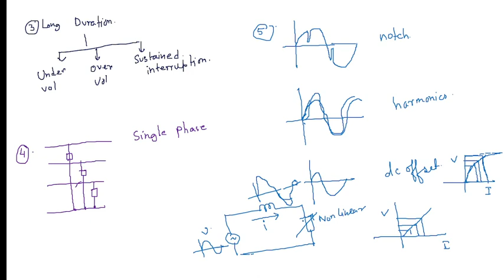So what happens? Though the voltage is perfectly sinusoidal, it creates a current magnitude which is not perfectly sinusoidal. Somewhere the increase of current is more with respect to the voltage, and the wave shape of the current may change. So this type of wave shape will contain harmonics. Though the supply voltage is perfectly balanced, due to the non-linear load, the current becomes different.